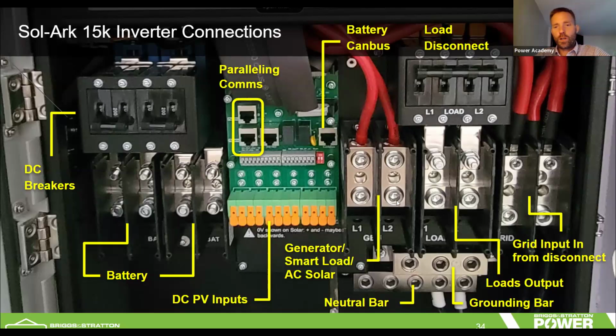The generator port is 80 amps continuous, 100 amp fused. And then your neutral bar and your ground bar down here at the bottom. Your load port is 200 amps here. This is a disconnect, not a breaker. So you do want to have a panel with an integrated 200 amp breaker on it. And then you've got a 200 amp input on the grid side as well that should be connected through a breaker.